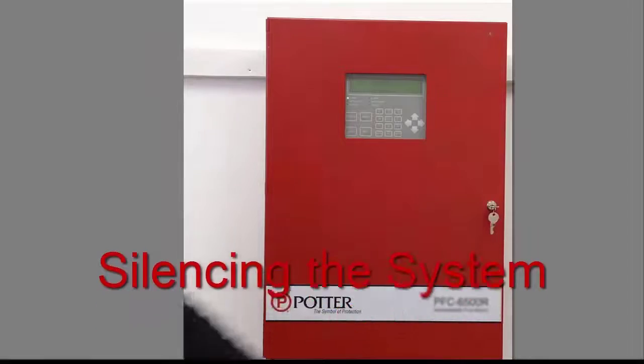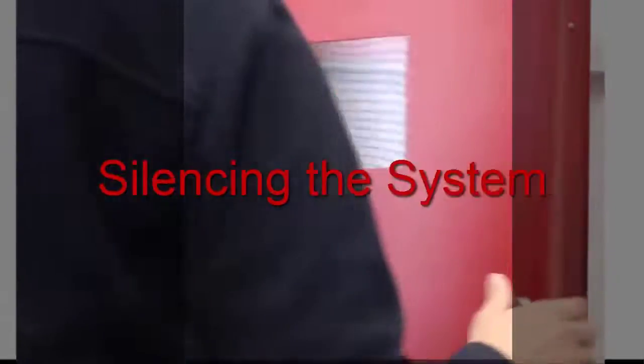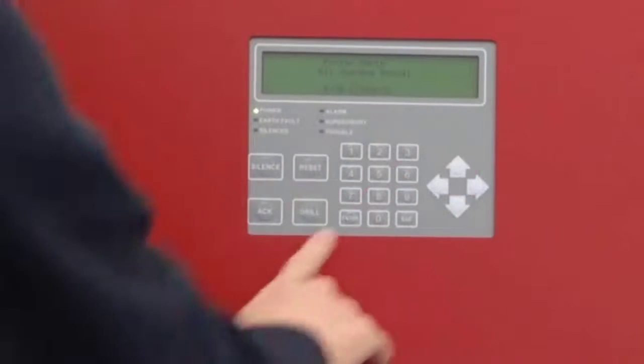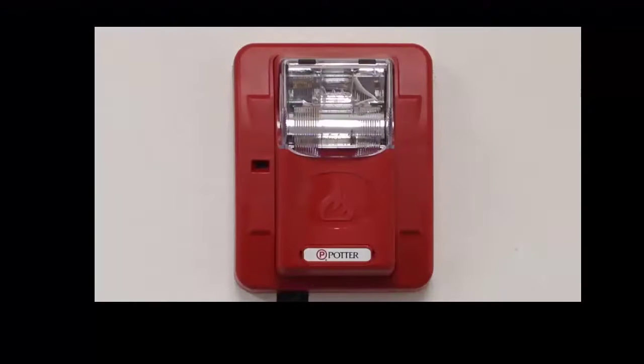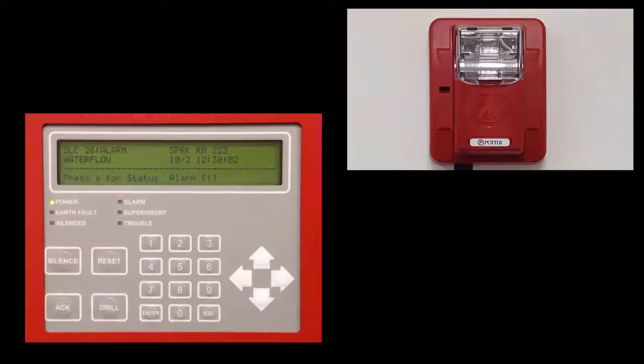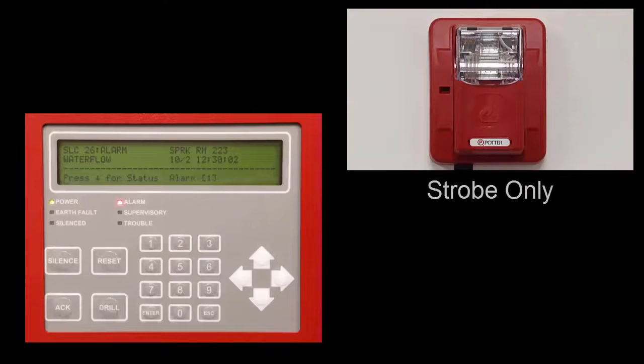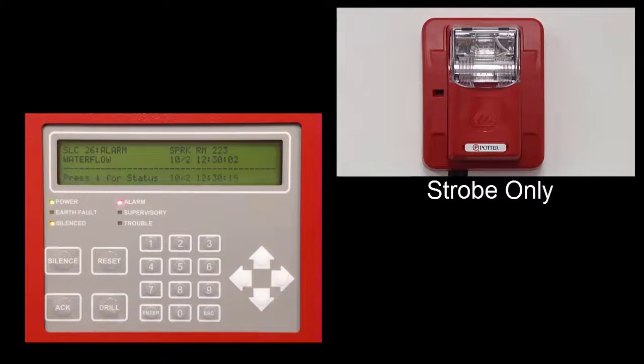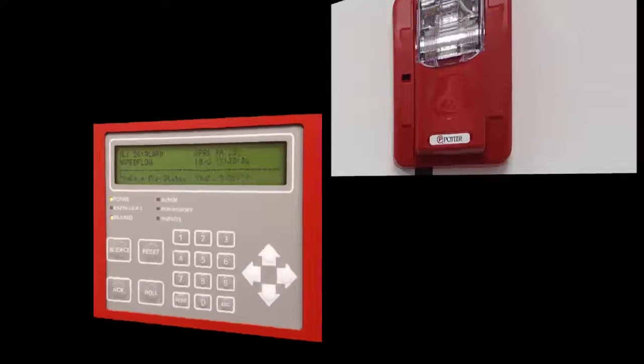Next, we will talk about silencing the notification devices in the field. When the notification devices are active, you can press the silence button on the front of the fire alarm control panel to turn the active notification off. Depending on how it is programmed, the strobes and horns may both turn off or just the horns may turn off. This demonstration is using a strobe-only device. When the silence button is pressed, the strobe turns off.